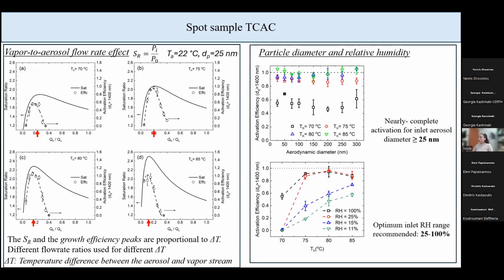The next thing that I tested was the activation efficiency as a function of the aerodynamic diameter of the aerosol that acted as nuclei. And I saw that in most cases at water temperatures of 75 degrees Celsius and higher, we can get nearly complete activation down to 25 nanometers. The optimum inlet relative humidity range that is recommended for this setup was 25 to 100% for the aerosol flow.